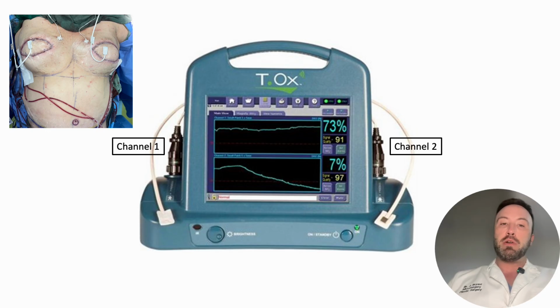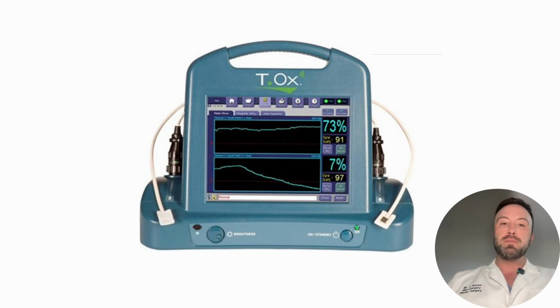The ViOptix monitor provides information on the flap oxygenation or perfusion. The signal quality value tells us whether or not the sensor probe is getting a good signal from the flap, telling us the reliability of the signal. Our goal for signal quality is greater than 80%. Things that can cause a poor signal quality are fluid between the probe and skin, poor contact of the probe to the skin, and bright lights.